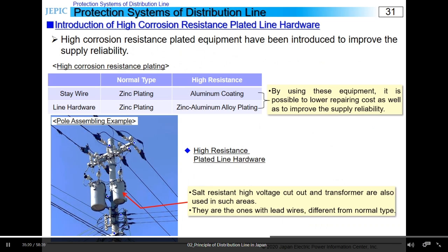The other equipment used in such areas is also designed to withstand pollution. For example, highly corrosion-resistant plated equipment has been introduced to keep the reliability. By using such equipment, it gets more unlikely to rust, and the mean time between repairs can be extended, as well as the supply reliability can be improved. In addition, for some equipment like transformers or high voltage cutouts, the ones with lead wires are used, different from normal types, so that the leak current can be suppressed to prevent a failure.